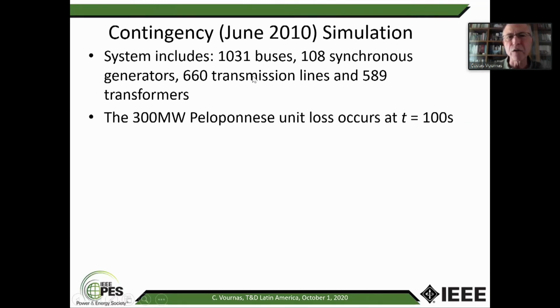So in simulating this, we simulate the whole system. It's more than 1,000 buses. Some call it a large system, some call it a small system, but this is what it is. We have more than 100 synchronous generators. I'll show you the effect of some wind farms in the Peloponnese, but these were part of the proposed ancillary service that we're going to show in case these farms were really providing something. Otherwise, they were modeled as passive loads, negative loads in the sense they were producing, but constant P and constant Q.